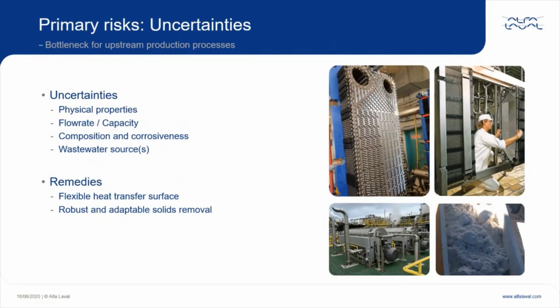Of course, we will use all means to get the best possible design basis for the process, such as computer modeling based on water chemistry, bench scale tests to determine important physical properties, but still it is very beneficial to use technology which is adaptable and robust for the CLD system. The plate and frame technology provides such adaptability and flexibility, since the heat exchangers can easily be modified after installation by adding or removing or replacing plates to achieve similar performance and fouling resistance for a new set of operating conditions. This type of modification is not possible with shell and tube heat exchangers without replacing the entire heat exchanger.